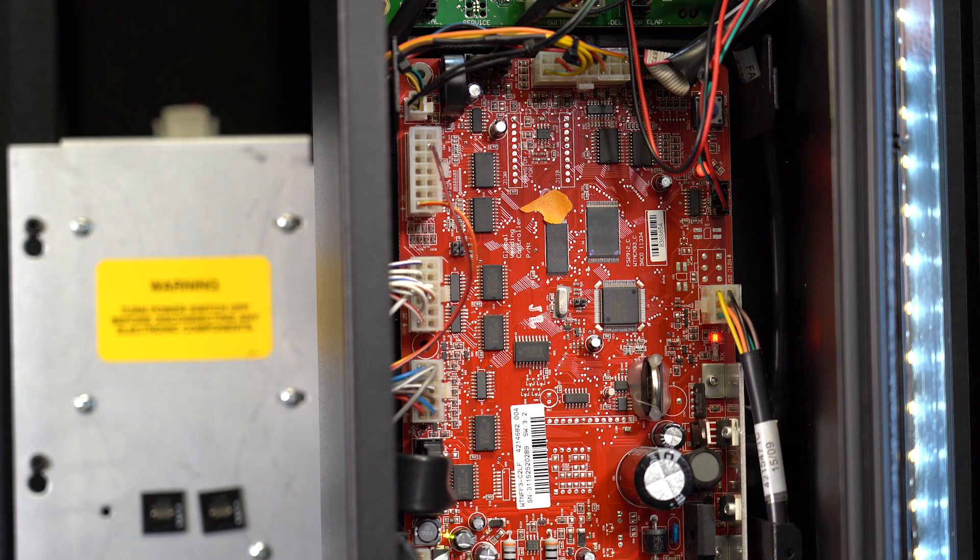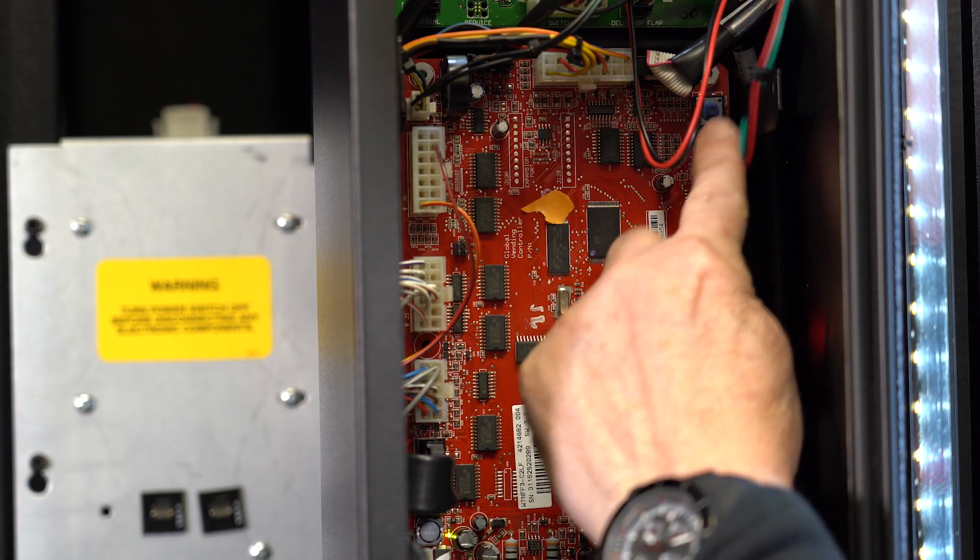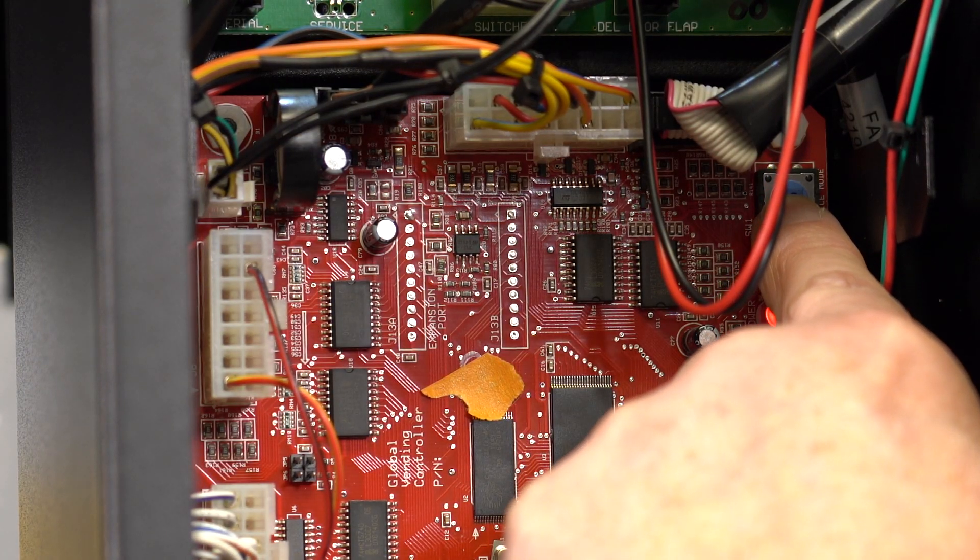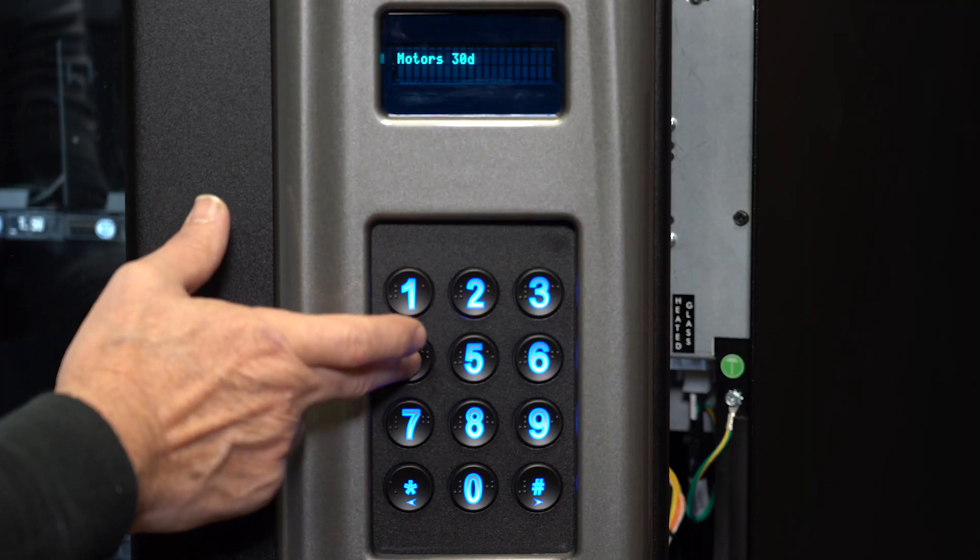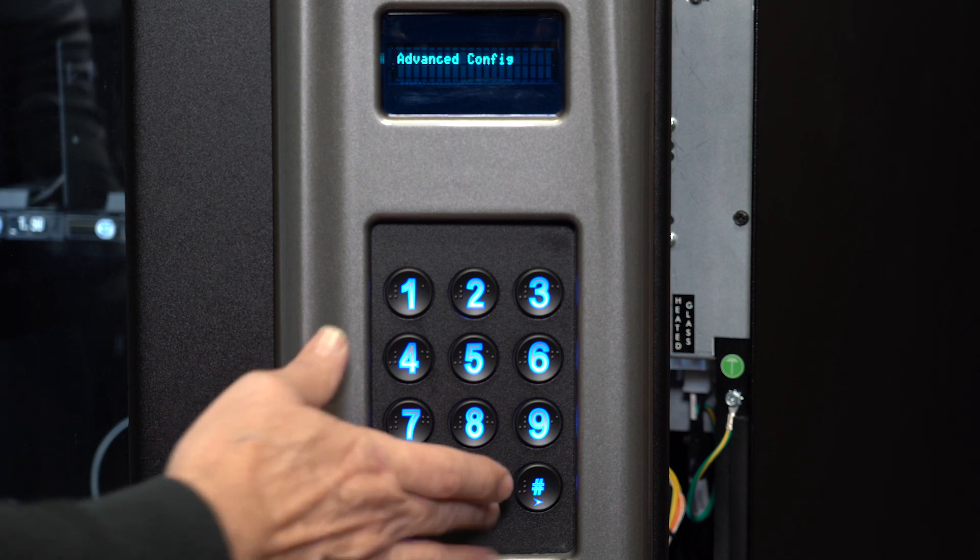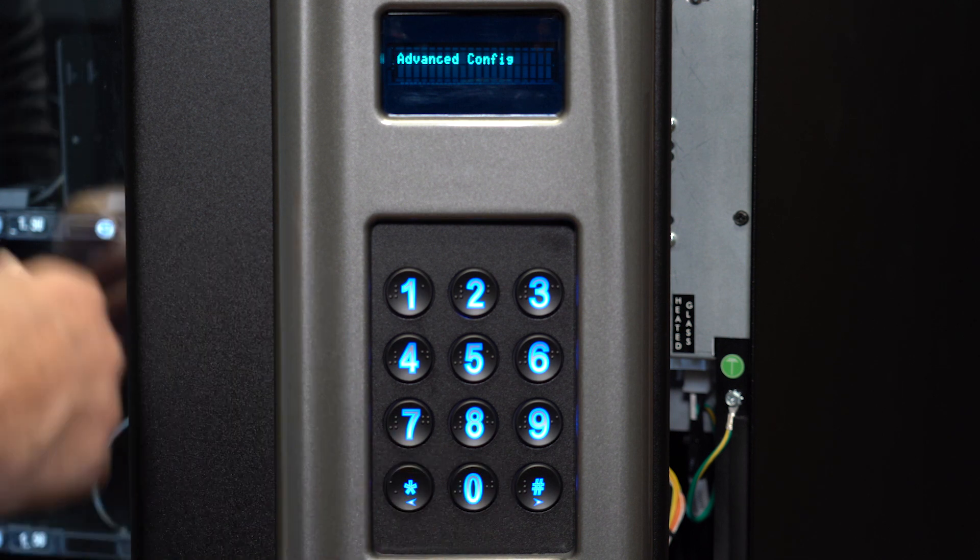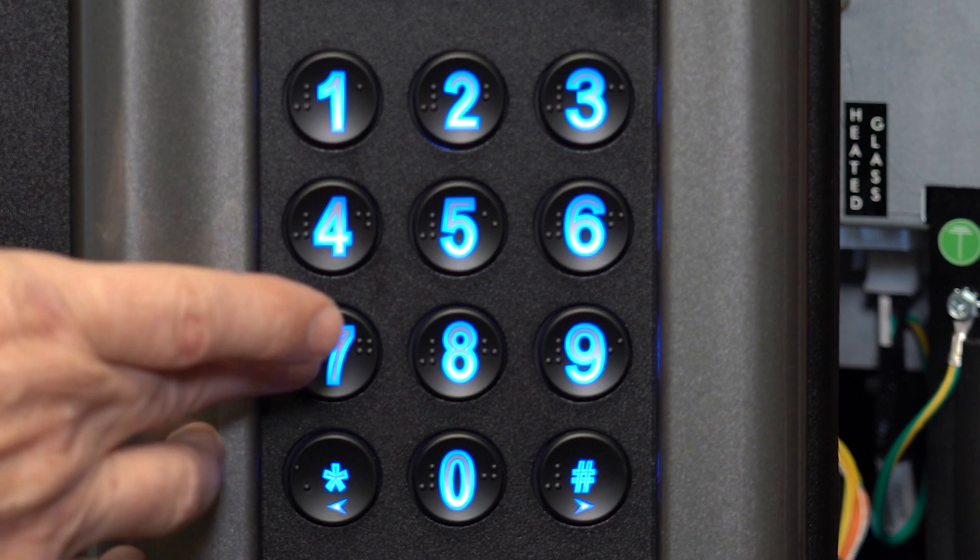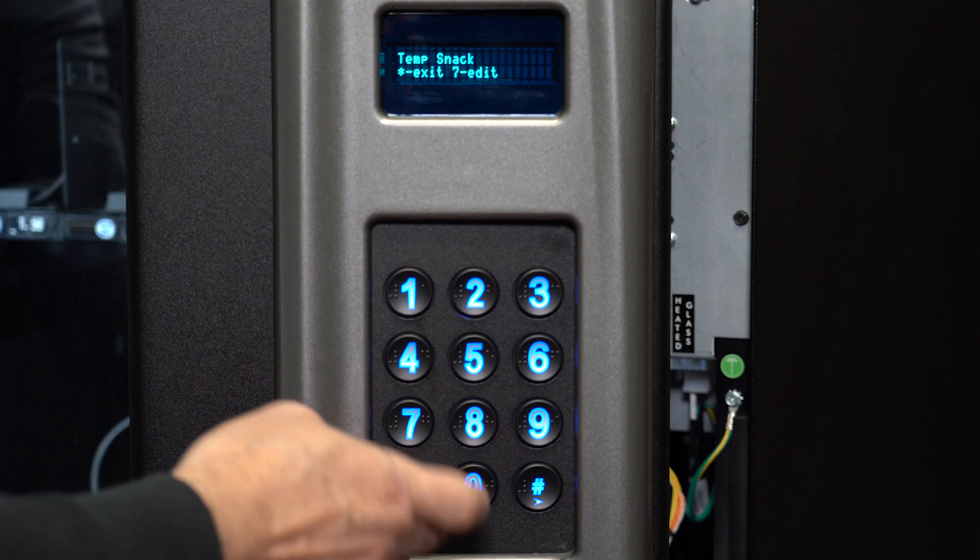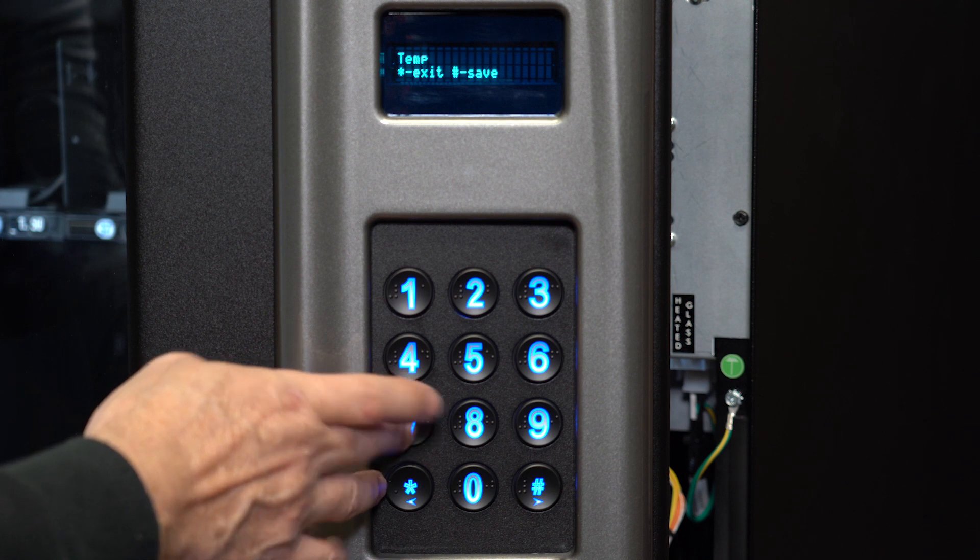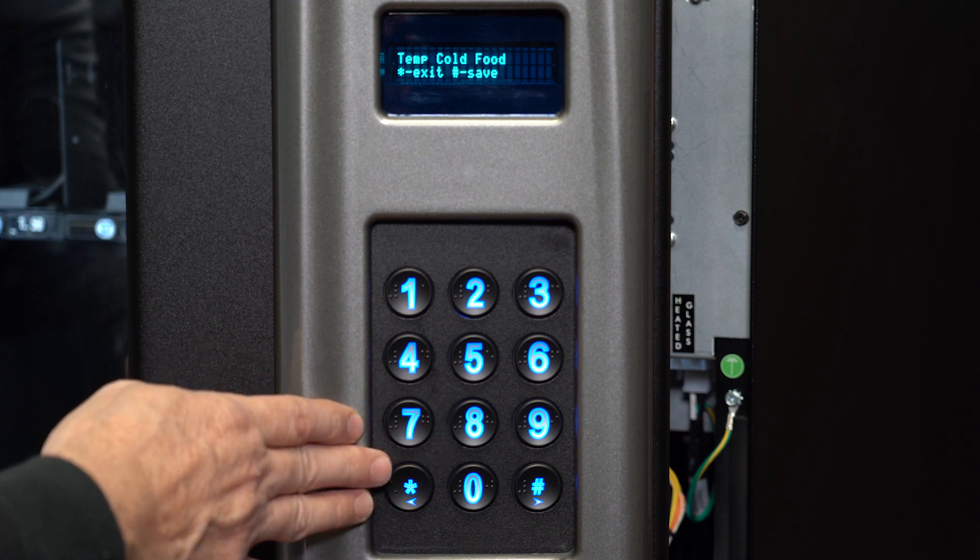If the machine is still not cooling, make sure the machine has correct settings. Enter service mode by pressing this button on the control panel. Then press 4 for the configuration menu, then press 0 for the advanced configuration menu. If you are unsure the password to your machine, try 2314. Press 7 to access temperature settings. If the temperature says snack, you can press 7 to correct it to cold or press 7 again to correct it to cold food.